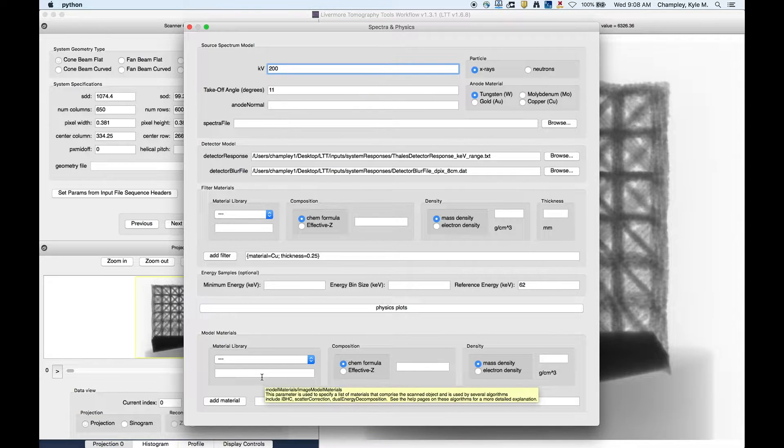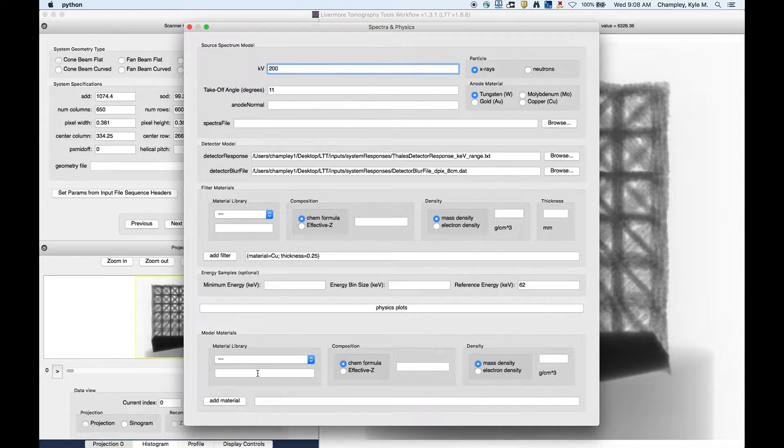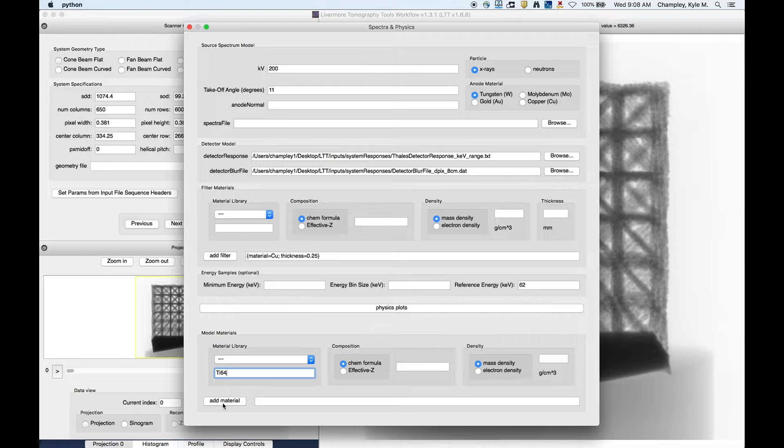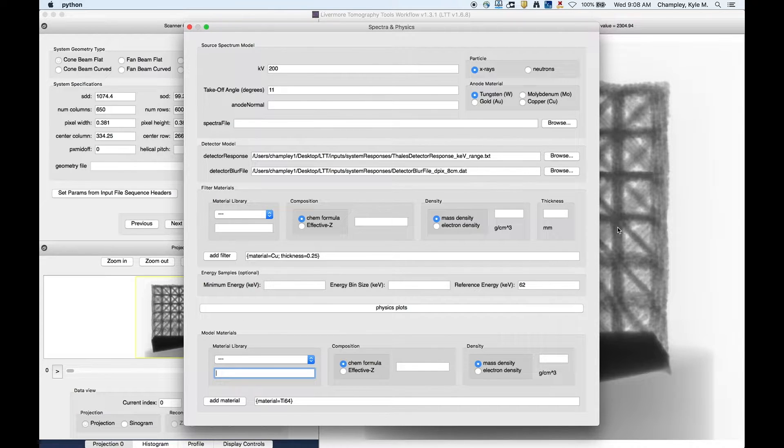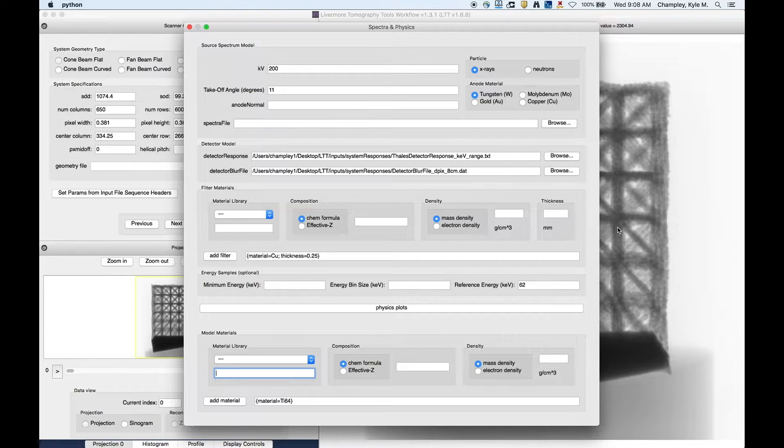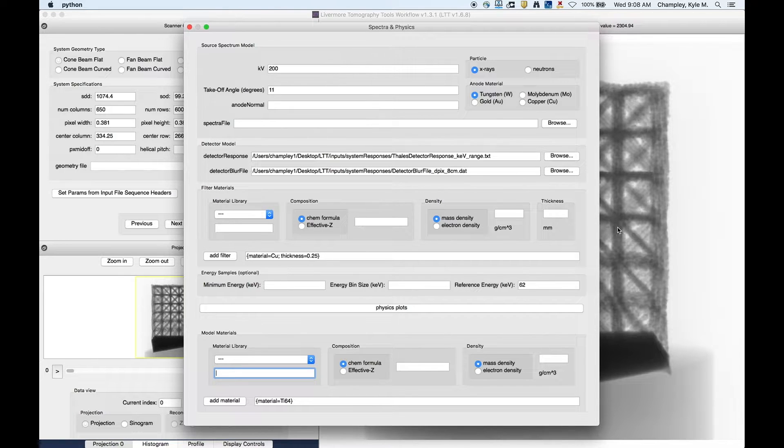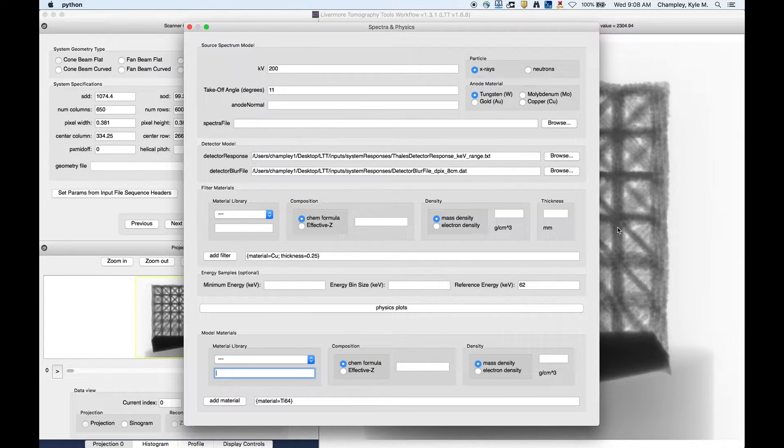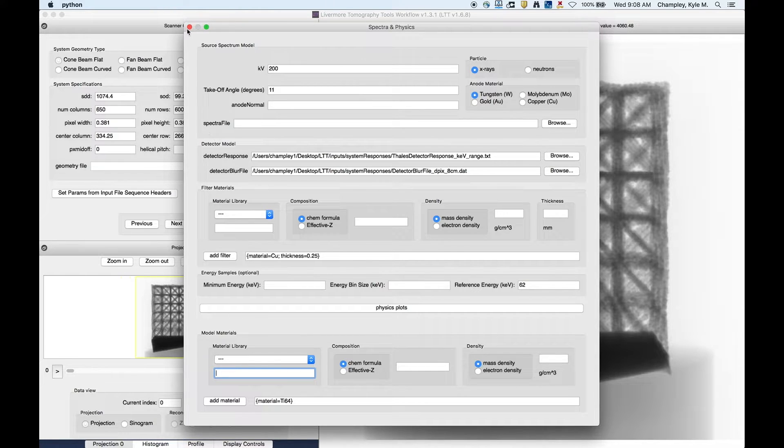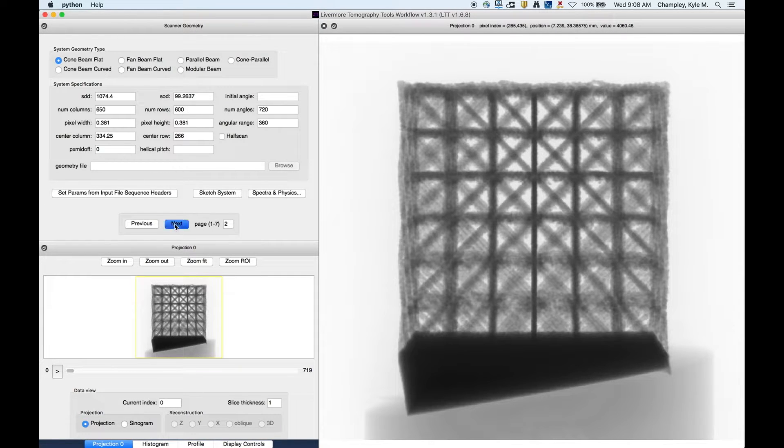Okay, the last thing that we need to specify, which is not in the SCT, is the materials that we expect to see. Now, this material is just one material, and it's TI-64. This is actually in the material library, so I type TI-64, I type add material, and now LTT knows that the material is titanium. Now, it's going to use this for a few things. It'll use it for the scatter correction, which is not totally critical that you get the material exactly right. It can be a little off, and it'll still do good. But it also is needed for the beam hardening correction. And the beam hardening correction is a multi-material beam hardening correction if you need it. And there you would list the multiple materials. So we have that specified. So we can close this, go to the next page.